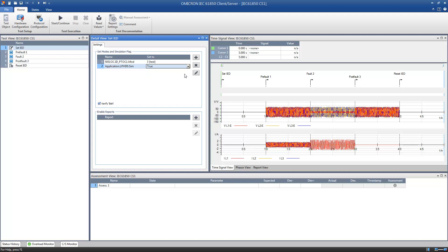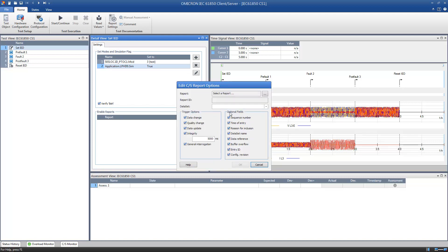An IED can use so-called reports to inform the control center about an occurring event. These reports are triggered by predefined trigger events. The information within a report is grouped in so-called data sets. To be able to access a report during the test, you have to activate a report in the state Set IED.